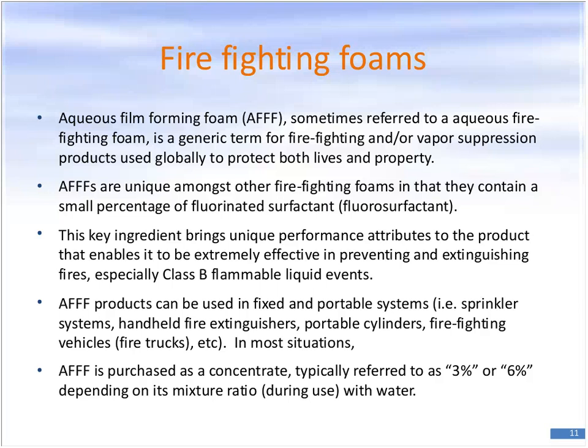AFFF are unique among other firefighting foams in that they contain a small percentage of fluorinated surfactants, fluorosurfactants, and these key ingredients bring unique performance attributes to the product, which enables it to be extremely effective in preventing and extinguishing fires, especially Class B flammable liquid events.